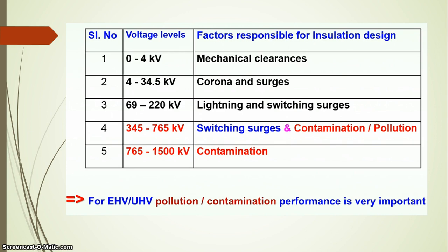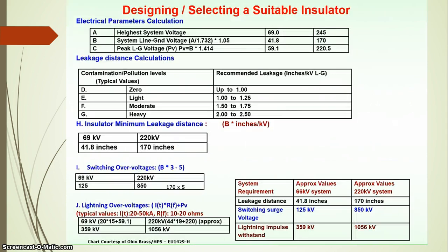From 765 to 1500 kV, contamination is the only factor on which insulator design is based. Above 345 kV is extra high voltage and above 765 kV is ultra high voltage, where pollution and contamination performance is very important.